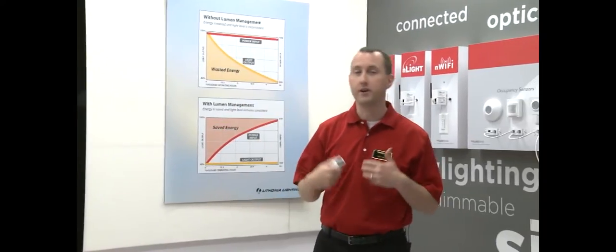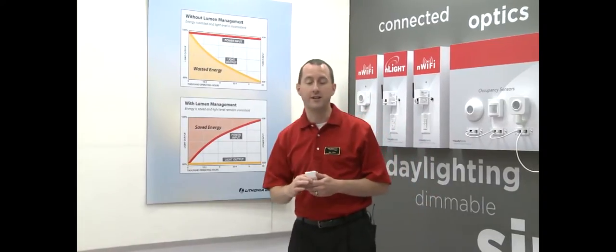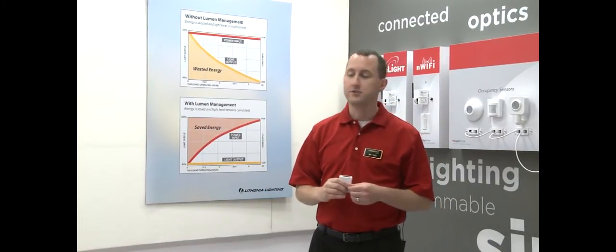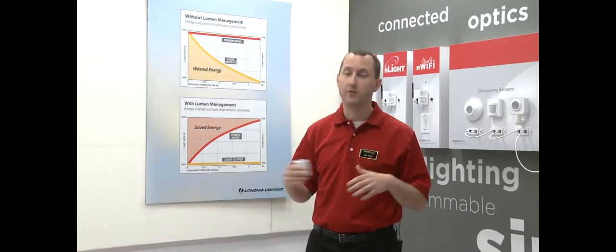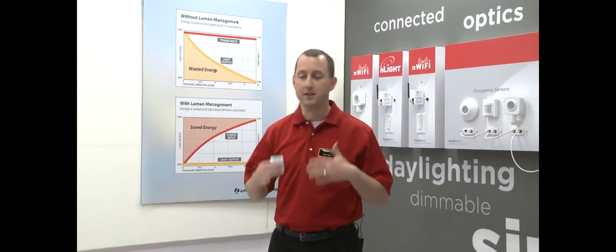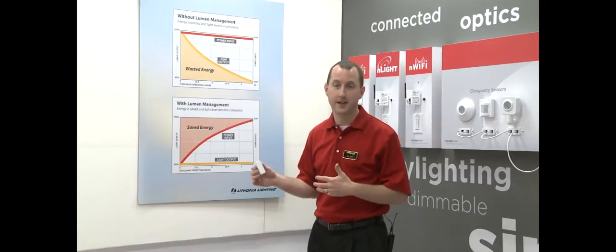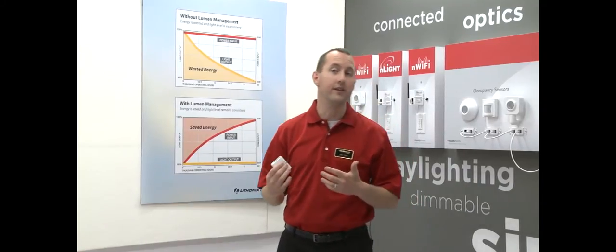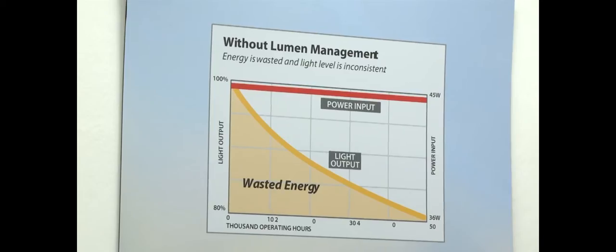The first thing it provides is what we call lumen management. Lumen management takes advantage of the common practice that traditionally lighting designers will design a space for maintained lumens because they need to compensate for the fact that over time, the lumen output of a fixture will decrease. So day one, they're actually over lighting a space. Well, obviously, if you're over lighting a space, you're wasting energy.